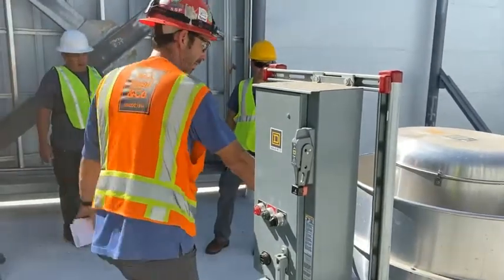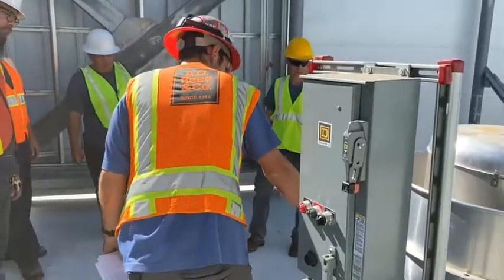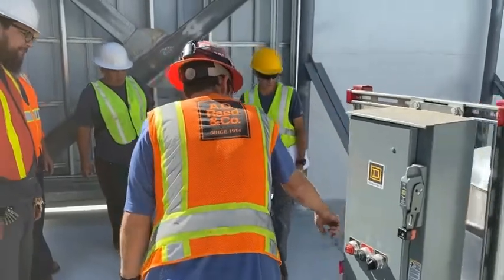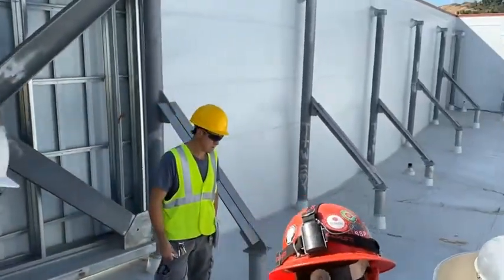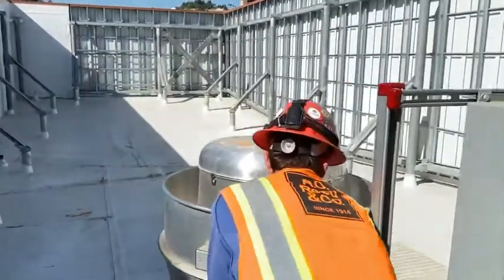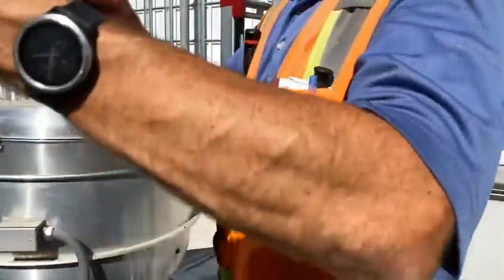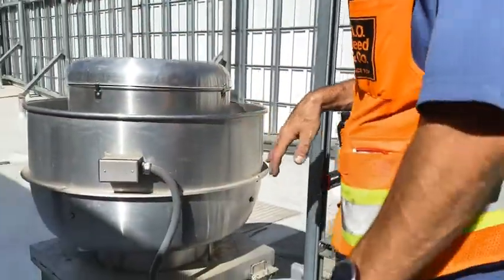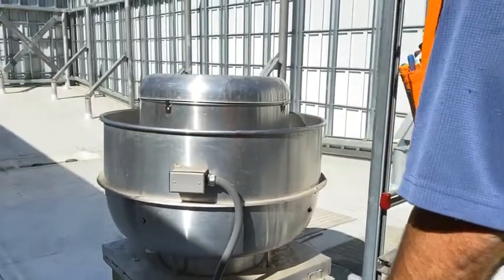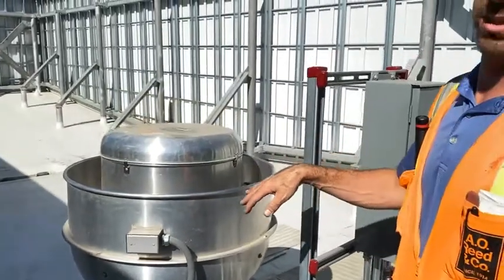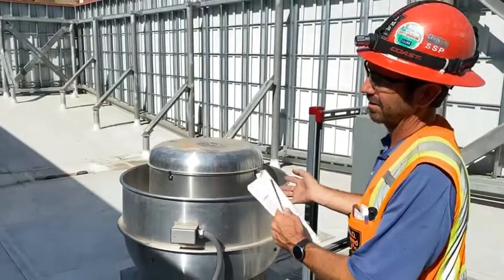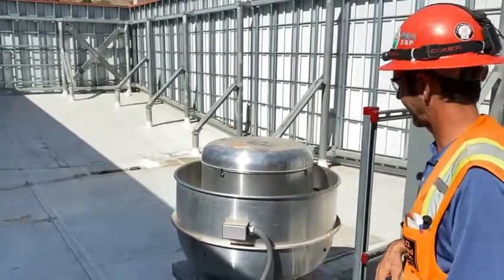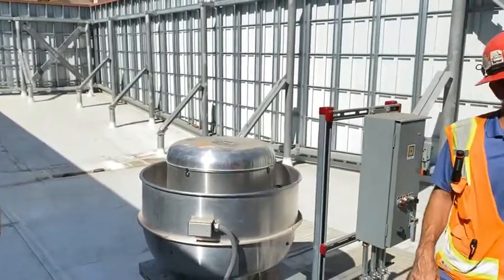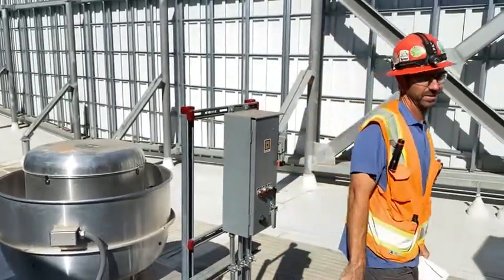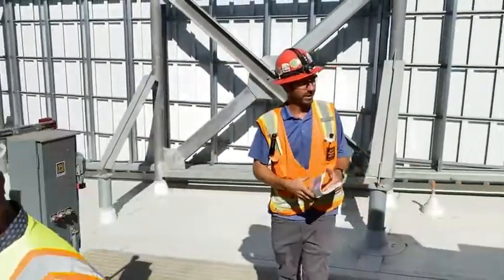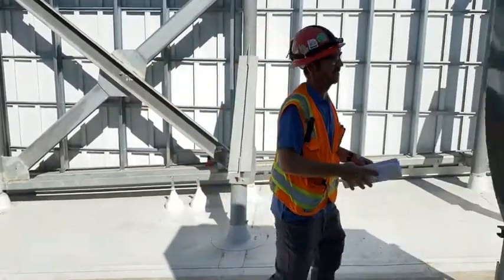There is an inspection hatch. There's hinges on one side. On this inspection unit, you can take the 2 bolts, there's 2 bolts right here. Undo those, and this thing will fold up to do wheel cleaning and to check the wheel. Okay. No backdraft damper on this unit. It's a grease fan. You can't have any type of device on top that would catch the grease. Okay. We'll move on up to this fan right here. This is EF1D. This is also a belt-driven unit.